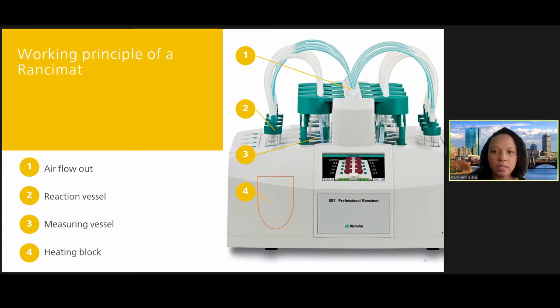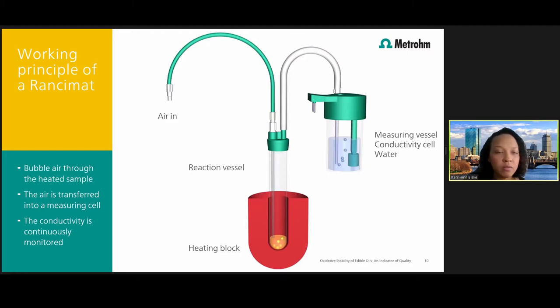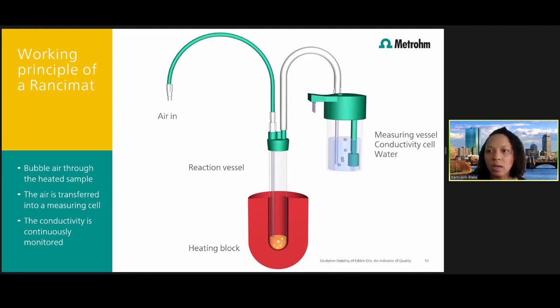The operation of the Rancimat is fairly simple. The sample is weighed into the reaction vessel, and the measuring cell is filled with distilled water. We connect the lids and tubes, and then the determination can be started. During the analysis, the sample is kept at a constant temperature in a closed reaction vessel, and a continuous flow of air is passed through the sample. Peroxides are formed as primary oxidation products via oxidation of fatty acids. After some time, the fatty acids are completely destroyed, and low molecular weight organic acids such as formic or acetic acid are formed as secondary oxidation products, along with other volatile organic species. These secondary oxidation products are conducted by air flow into a measuring vessel containing distilled water as an absorption solution.